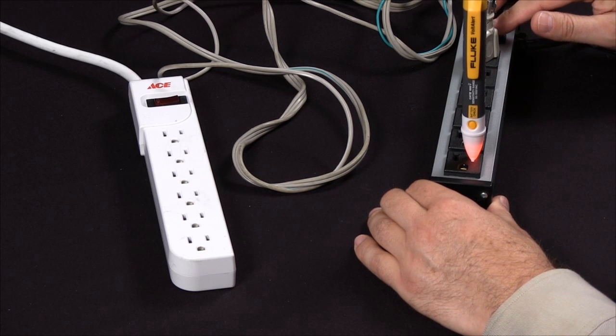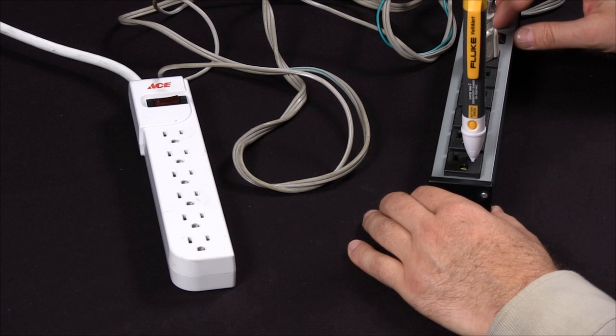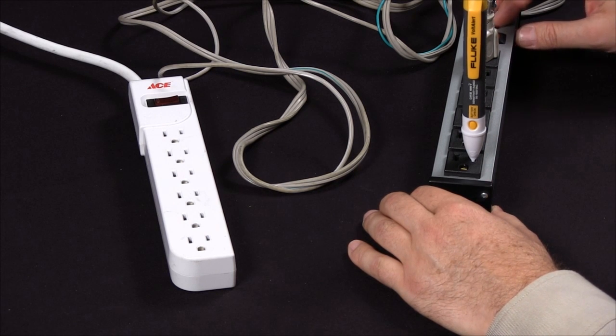Now when I do have power and I break the circuit, thereby indicating an open circuit, how can I be sure that I do not have power and it's not the battery in the Volt Detector itself?